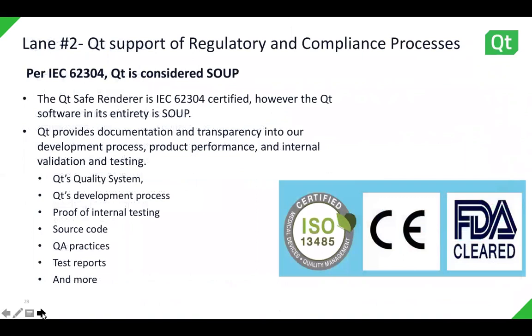So let's look at lane 2. Lane 2, Qt supported regulatory compliance processes. We say this a lot on our website, in our literature, in our day-to-day conversation. What does this mean? Well, per IEC 62304, Qt is still considered software of unknown provenance, SOUP. Although the safe renderer, as we discussed, is 26262 certified, Qt in its entirety is SOUP.